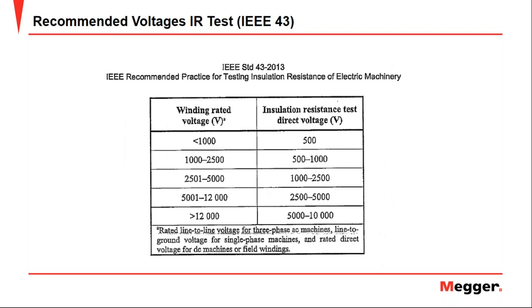Now, what are the recommended voltages for the insulation resistance test? At what voltage level should the insulation resistance test be performed? In the IEEE 43 standard, it is indicated by the following table. What is the value of the voltage that must be applied in DC depending on the nameplate voltage? As you can see, for each level of bus voltage, there is a range of voltages that can be used to perform the test. Let's take an example.